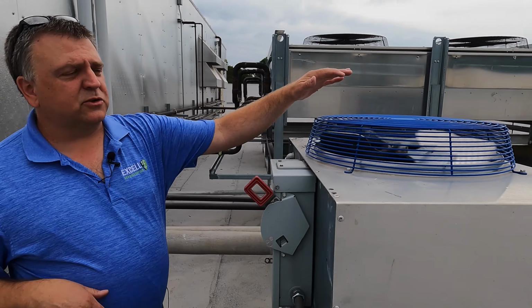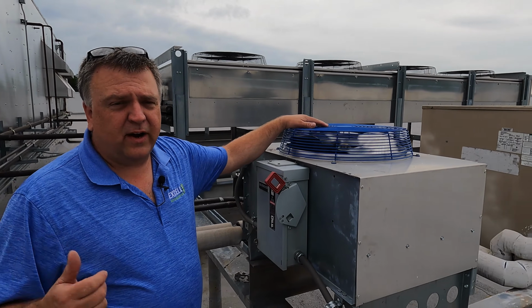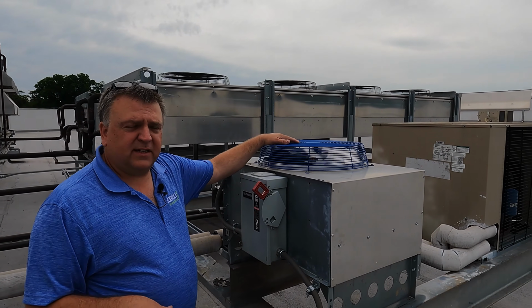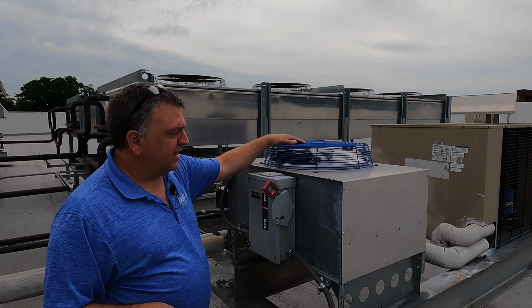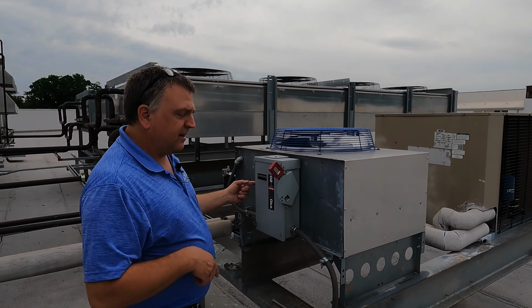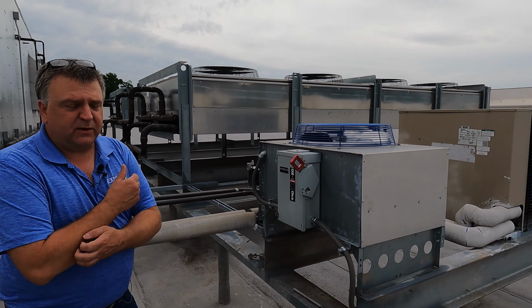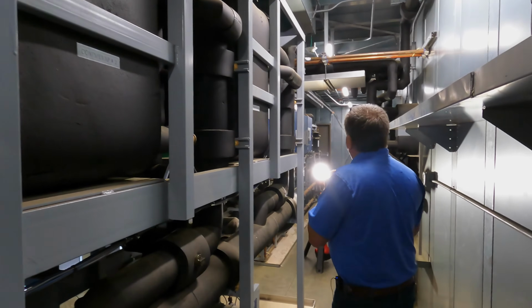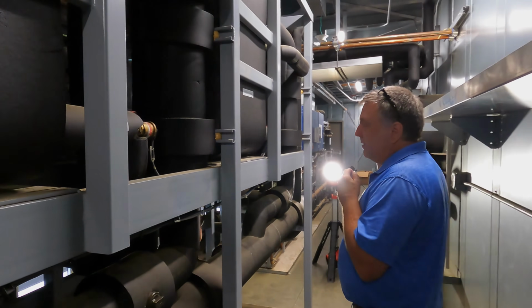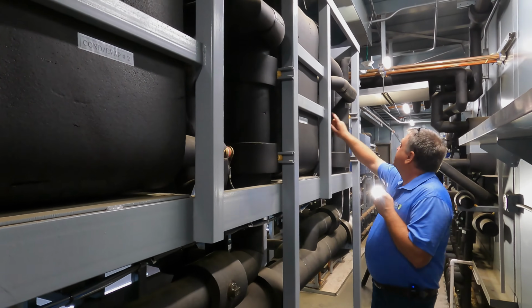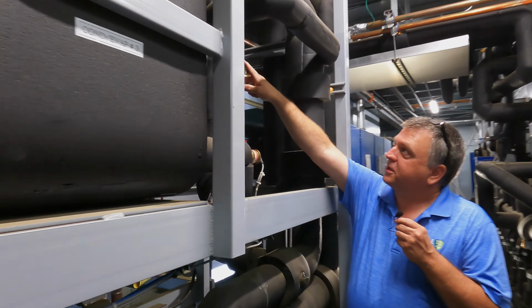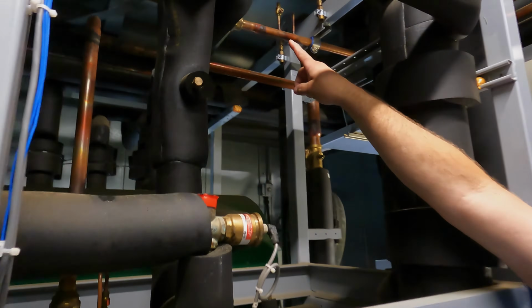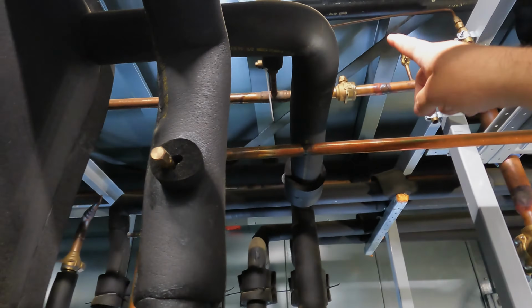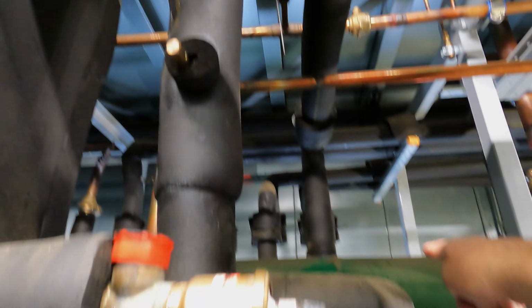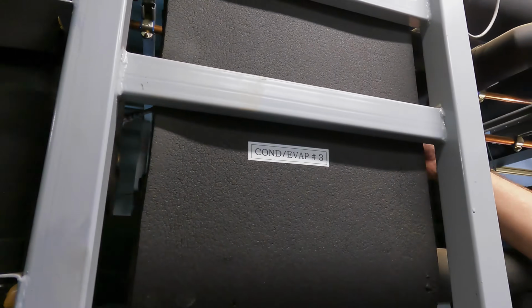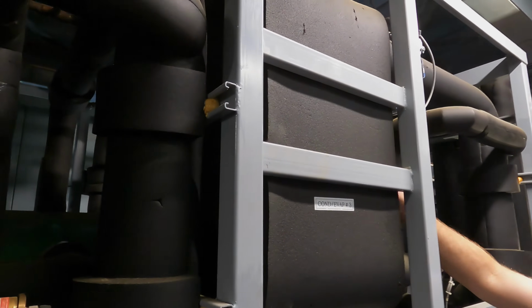Now, the only thing that controls this is an outdoor air sensor. If my outdoor air sensor drops below 60 degrees, there's enough line set and enough coil room that it's going to remove the heat without the fan running. Now that we've gone through our de-superheater, we have that cool gas coming over here, and as you can see, it tees in to the top of where our vapor comes off the top of the vessel, and it goes into our chiller.